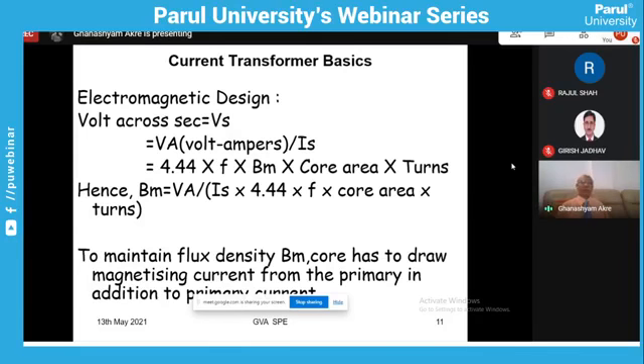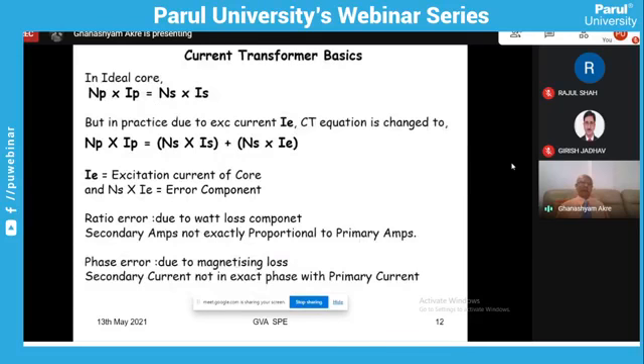You see, in actual current transformer, what happens now? In ideal transformer, number of turns in primary into the current flowing in it will be balanced by number of turns in secondary and the secondary current. So this is the ideal case where the ratio error will not be there. But in practice, due to excitation current, IE, the CT equation is changed to primary ampere turn, that is NP into IP, and that will be equal to secondary ampere turn, that is NS into IS, that is the external current which you are driving, and internally it will also draw in addition to that NS multiplied by IE. That IE is the magnetizing current drawn by the core.